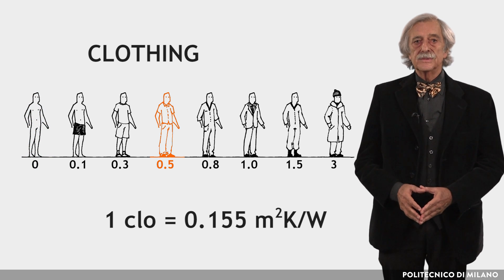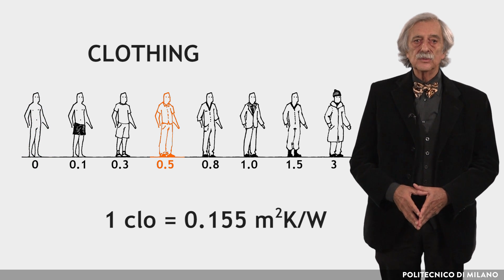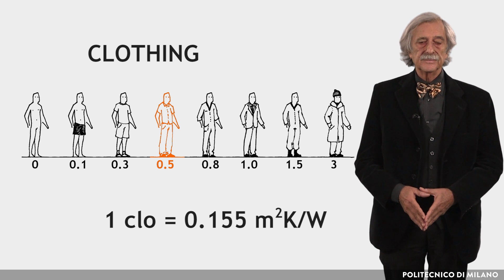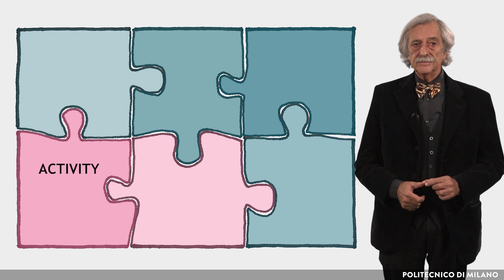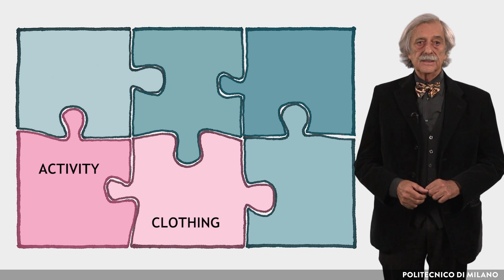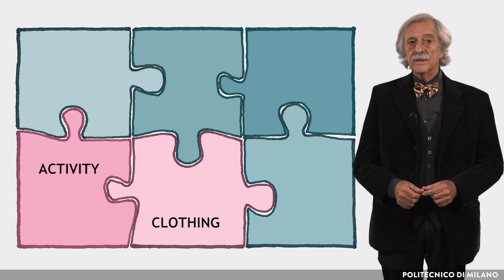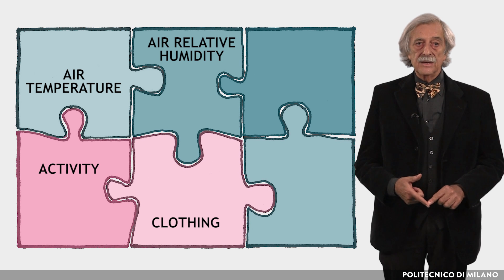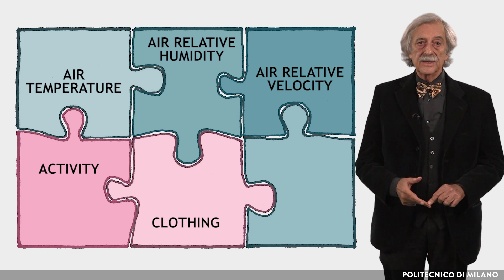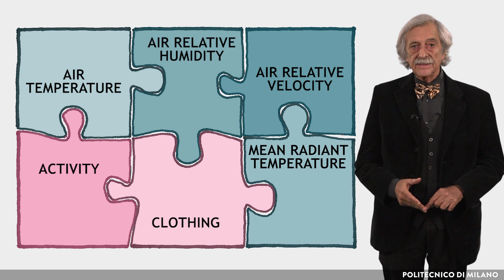The value CLO = 0.5 corresponds to typical summer clothing. Summarizing, the body's heat balance, hence thermal comfort, depends on six factors, of which two are personal and four are environmental. The personal factors are activity and clothing. The environmental factors are air temperature, air relative humidity, air relative velocity, and mean radiant temperature.